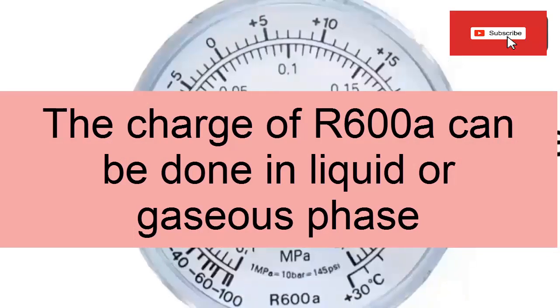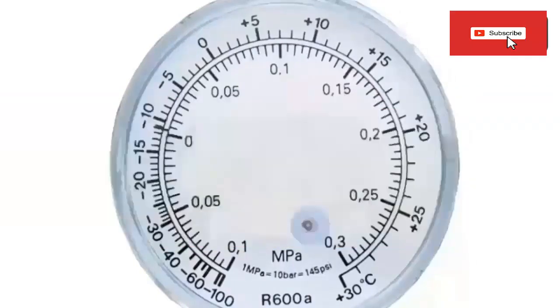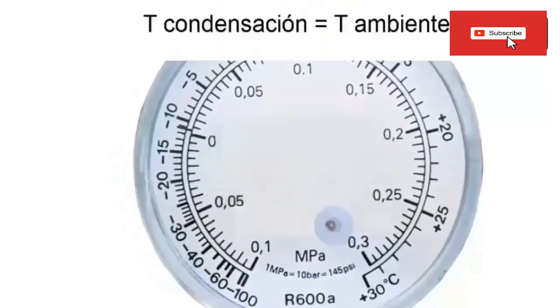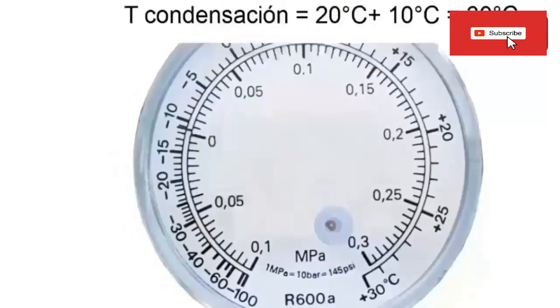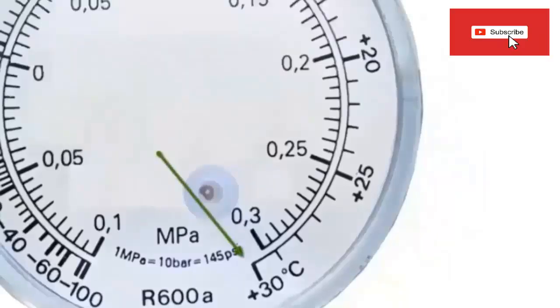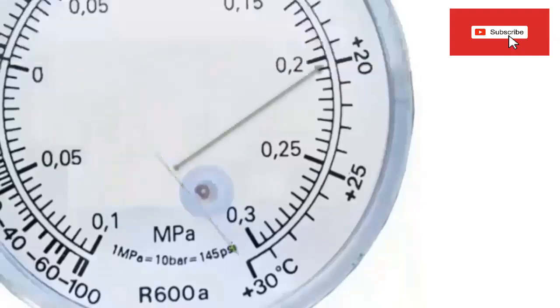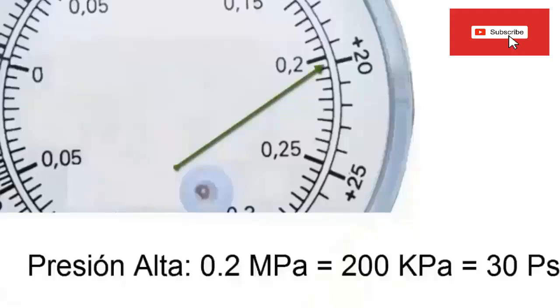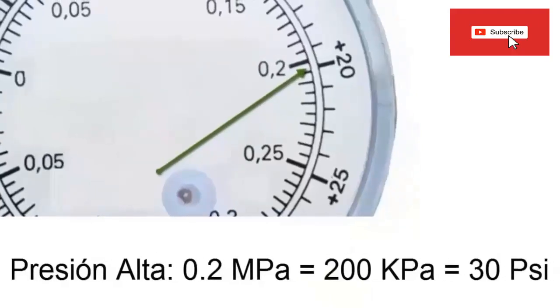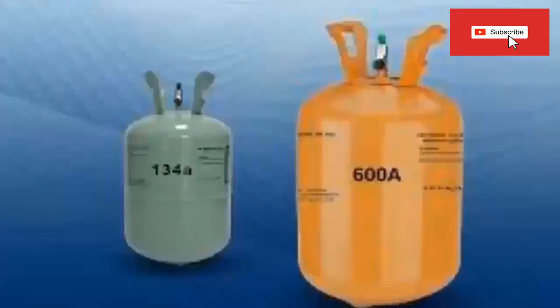R600a can be charged in both the liquid and vapor phases. For an environment of 20 degrees Celsius, we are going to have an average condensation temperature of about 30 degrees Celsius. Setting the needle to 30 degrees Celsius allows us to note the pressure value. If we want to know the pressure that the equipment should have when turned off, we search the manometer for the value of the ambient temperature, placing the needle at 20 degrees Celsius to read the pressure value.